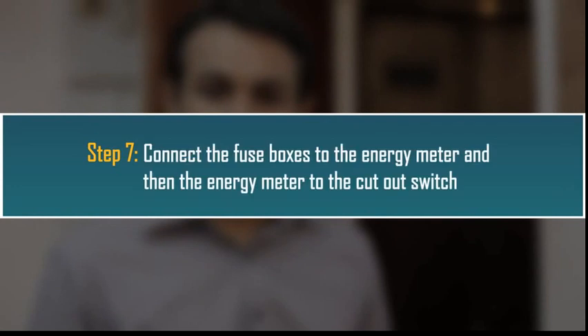Step 7. Connect the fuse boxes to the energy meter and the energy meter to the cutout switch. Now we need to connect the fuse boxes to the energy meter and the energy meter to the cutout switch. For that, we need to cut pieces of 2.5 square mm wire that we need to connect to the input supply board. Let us follow the phase color coding and connect all our wires.